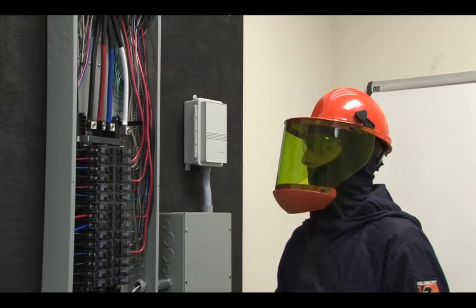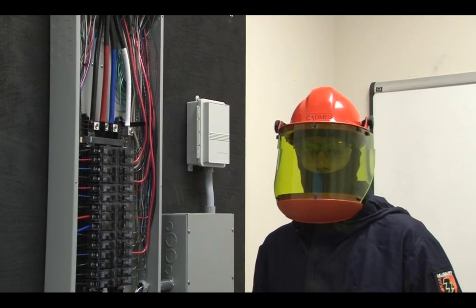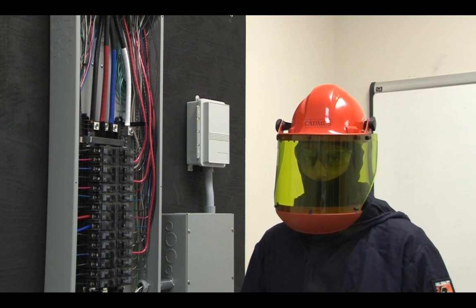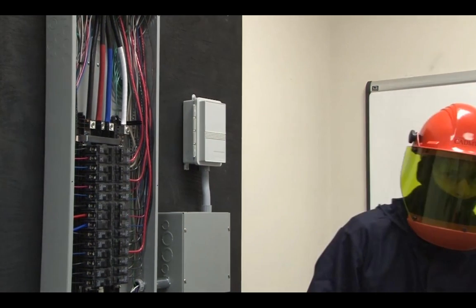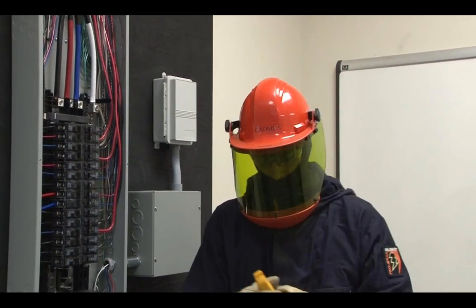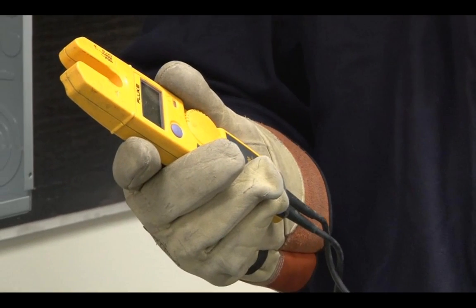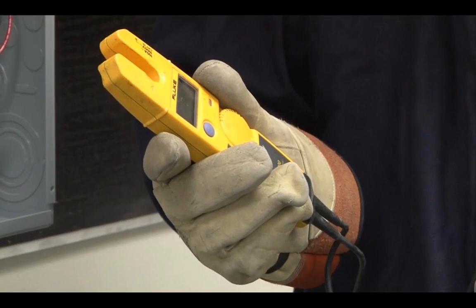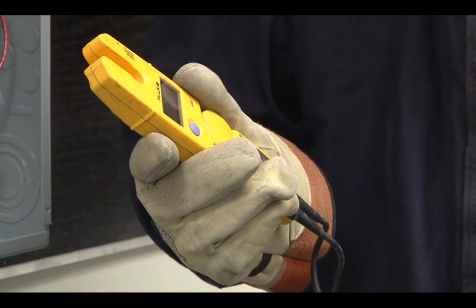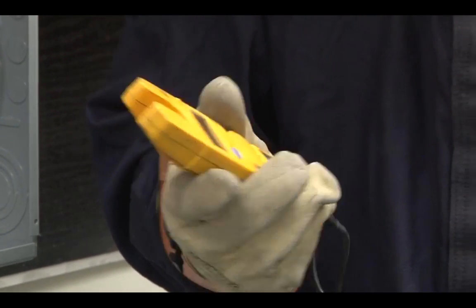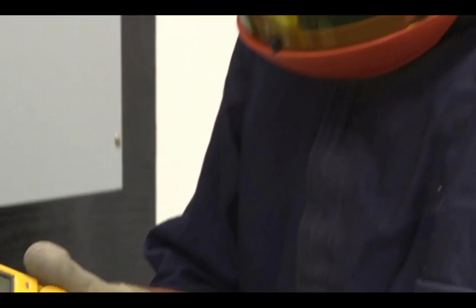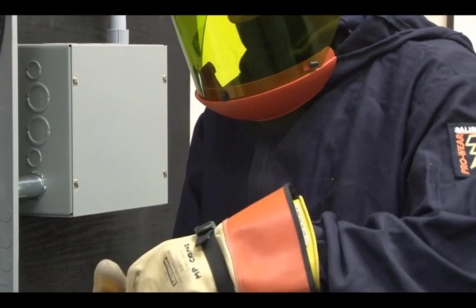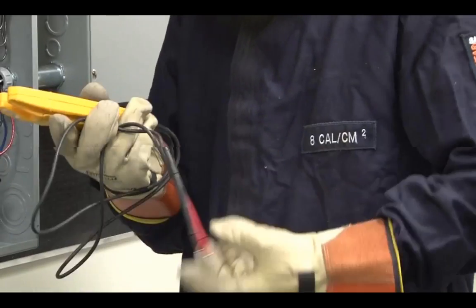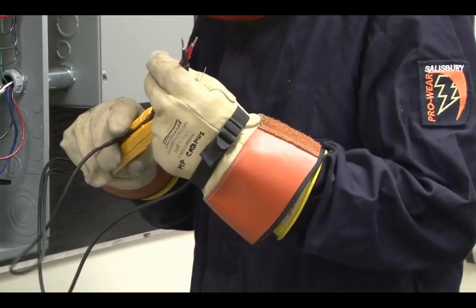We can see that the main conductors are black, red, and blue, so we know this panel is probably 208 volts. We'll confirm that with our voltage meter. We'll take our voltage readings with a Fluke T5 1000 meter. This is double insulated and good for up to 1000 volts. We'll set the meter to voltage, and we'll take multiple voltage measurements.